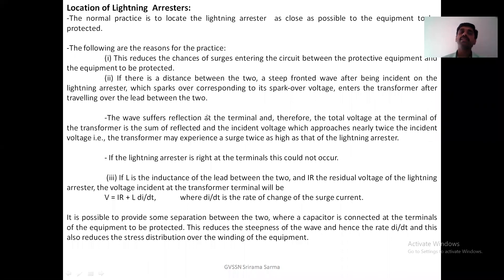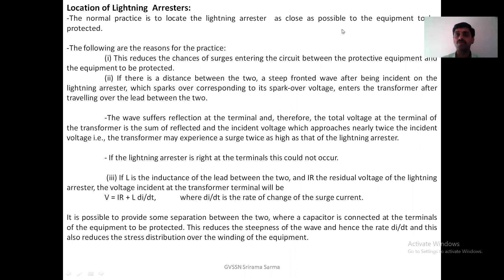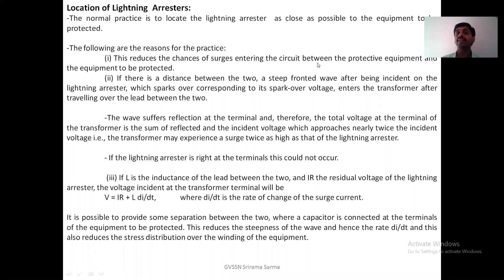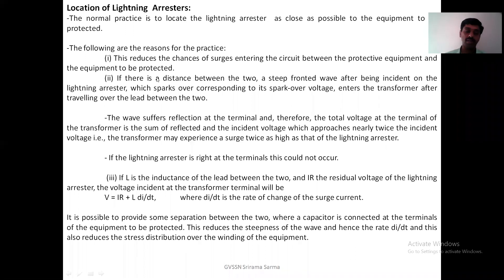Normal practice: these lightning arresters should be placed as close as possible to the equipment. Normally a lightning arrester will be placed near the transformers, generators — near to the equipment you have to place. Why? Because this reduces the chances of surges entering the circuit between the protective equipment and the equipment to be protected.